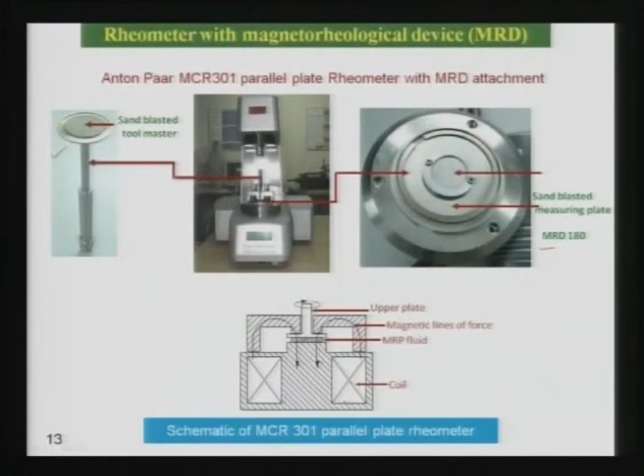You can see coils are there which create a certain magnetic field, and here is the MR polishing fluid. When this plate rotates, shearing action takes place, and with the help of the data provided by this rheometer, the yield stress and the viscosity of a particular composition of the MR polishing fluid are evaluated. With the help of this rheometer, you can find out the properties of the medium at different shear rates. You can also vary the temperature of the medium, because during the MRAP process or AFM process, the temperature of the medium changes as finishing keeps going on. So we should know the rheological properties of the medium at different temperatures also, and you can utilize this particular rheometer for that purpose.